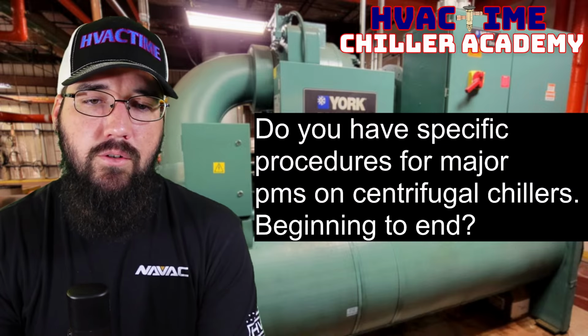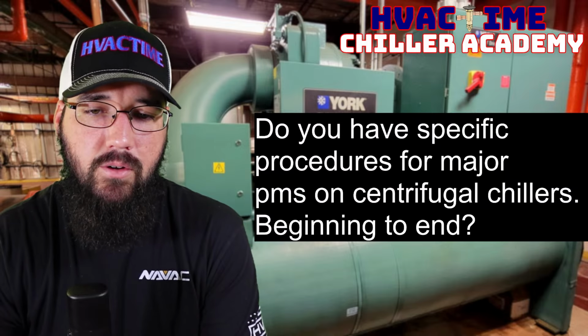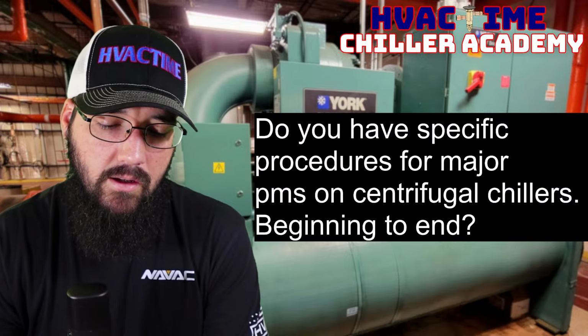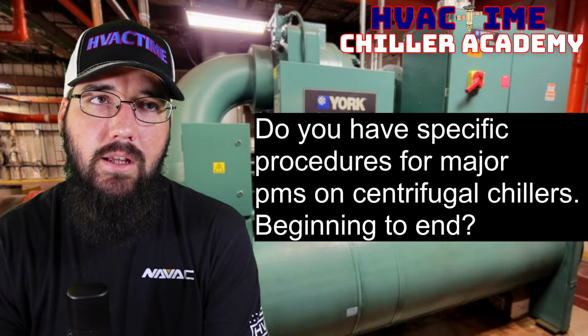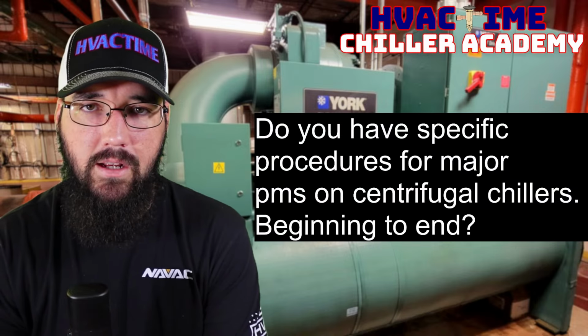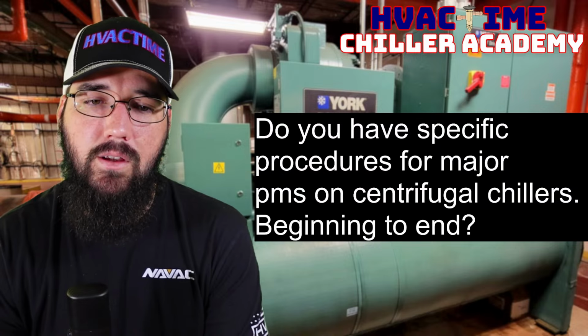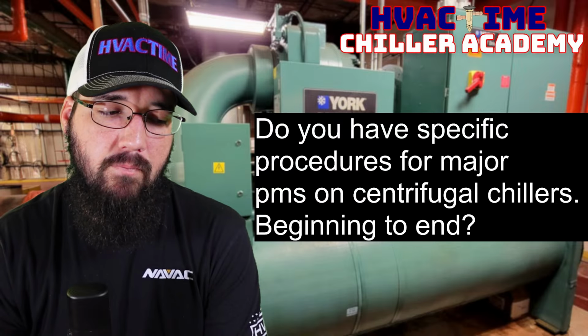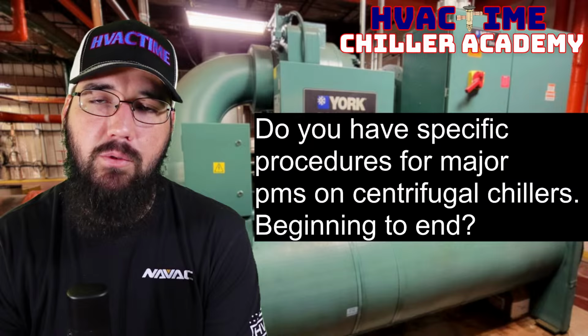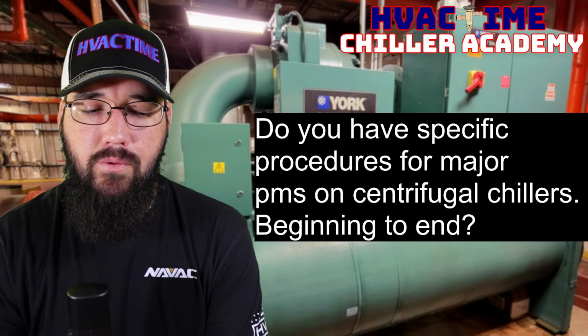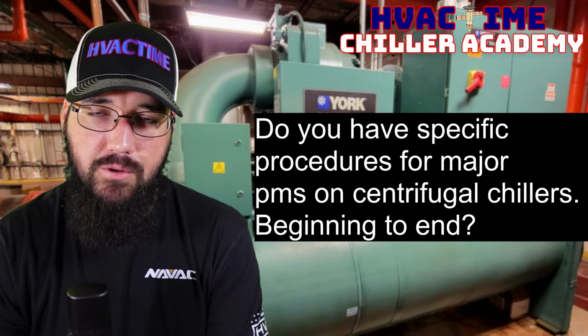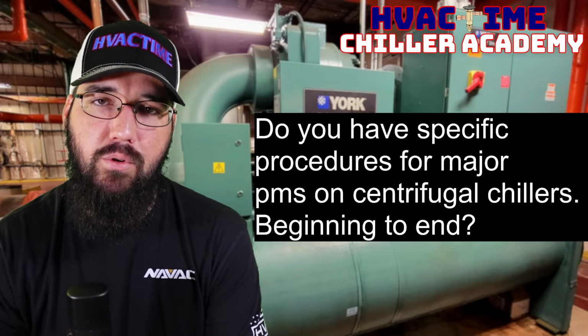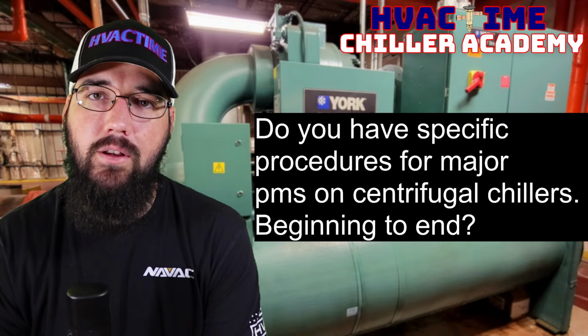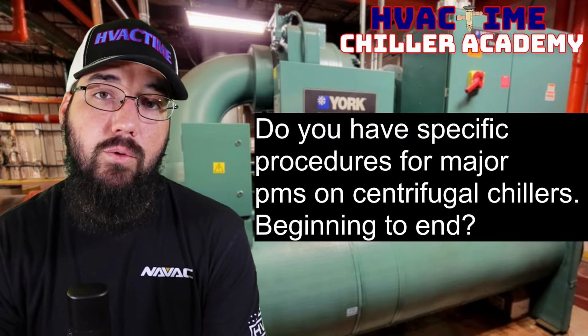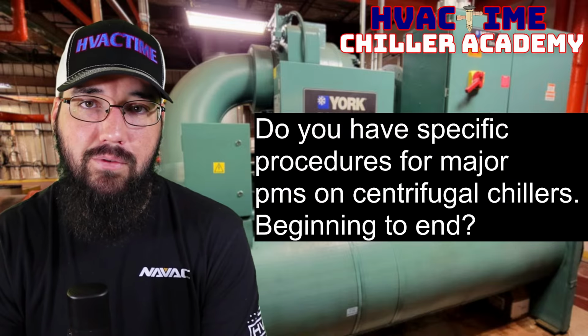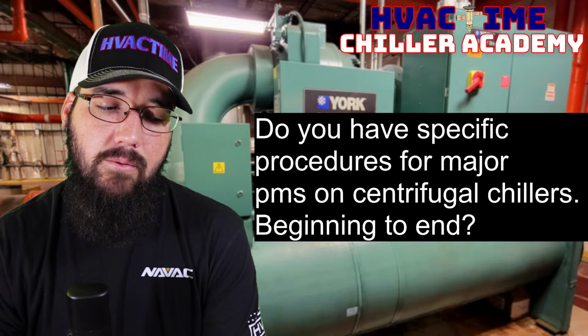All right. Do you have specific procedures for major PMs on centrifugal chillers, beginning to end? Yes. I have a flow that I like to do. From a basic PM standpoint, there is a difference between low pressure and high pressure. There's a very specific step that gets added with low pressure machines, where we have to pressurize the machine. Keep in mind, low pressure operates below atmosphere, so we're in a vacuum, and if we're going to do a leak search, we need to get the machine above atmosphere.